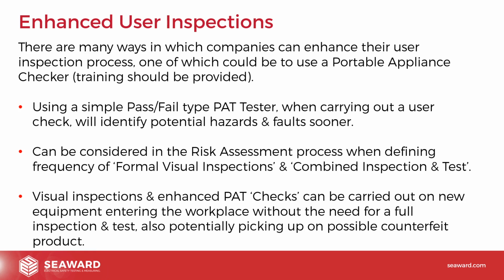So these can be considered in the risk assessment process when defining frequency of formal visual inspections and combined inspection and test. Visual inspections and enhanced PAT checks can be carried out on new equipment entering the workplace without the need for a full inspection and test, also potentially picking up on possible counterfeit products. So we think you could use this: somebody who's a level 1 person could use a basic PAT checker to screen equipment coming into the workplace. We're still saying it would get a formal portable appliance test in the testing interval defined by the duty holder. But often this equipment might just get a visual check, enter the workplace, and we're not sure, there could be a defect, there could be a problem, where it's counterfeit or something like that. And that would be picked up by just using a simple go, no-go PAT checker, really. So again, something for duty holders to think about is enhanced user inspections.